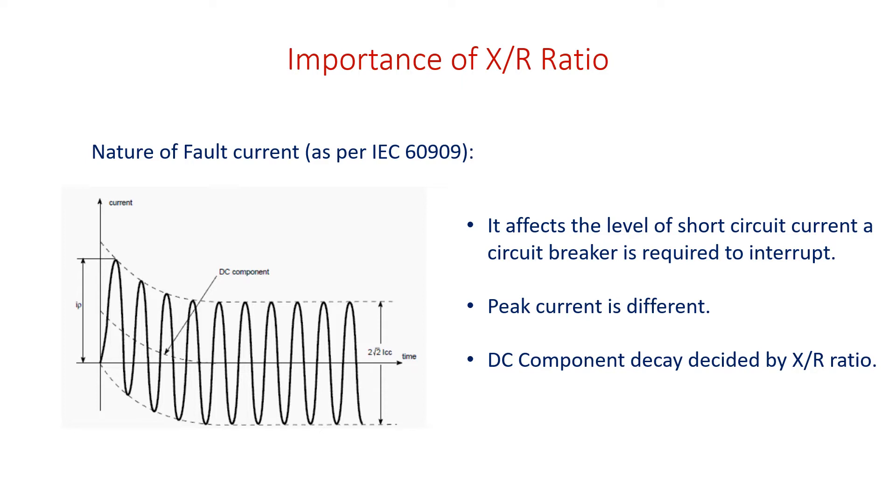X by R ratio affects the level of short circuit current a circuit breaker is required to interrupt. Peak current is different from RMS current and the level of DC component decay is decided by X by R ratio. Let us analyze these importance factors in the upcoming slide.